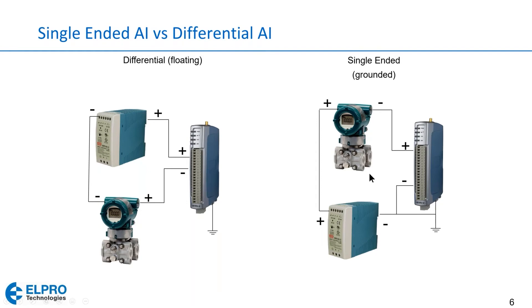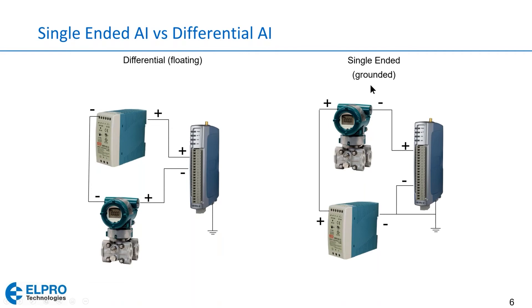If there is no option, we simply need to insert a loop isolator between the instrument and the radio's 4-to-20 milliamp input. With a differential or floating input, the instrument can be wired anywhere in the loop with no issue of potentially connecting to ground. That's the difference between a differential input and a single-ended or grounded input.